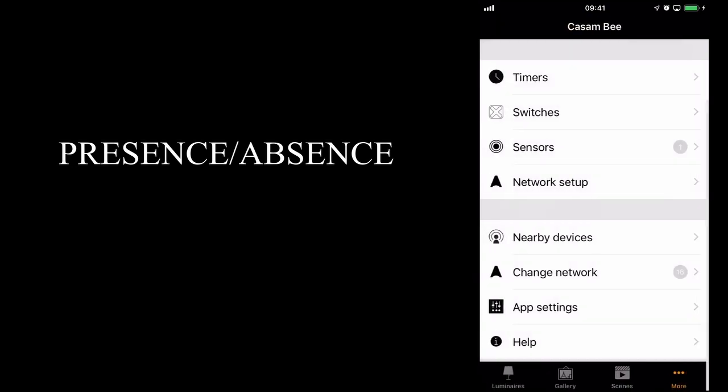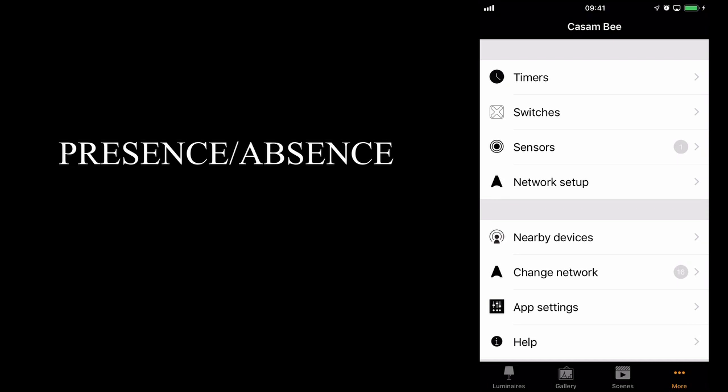The next option is presence-absence. The way presence-absence works is the presence scene and absence scene must control the same group of luminaires. It's not possible to control one set of luminaires for your presence scene and a different set of luminaires for your absence scene. The idea is that a presence scene may set the luminaire to 100%, and an absence scene may set the same luminaires to 20%, for example. So let's do that in our example.